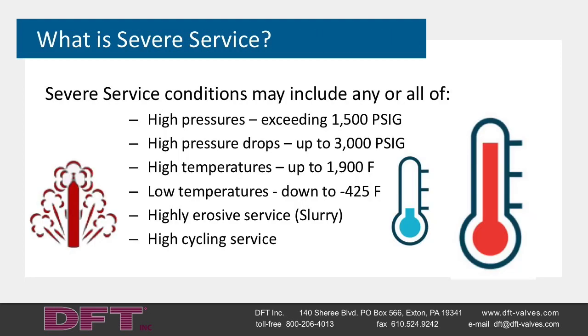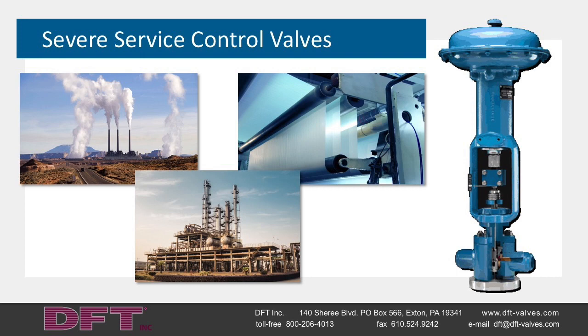What is severe service? Severe service is any service that results in excessive wear and frequent maintenance. Severe service conditions may include any or all of the following: high pressures exceeding 1,500 PSIG, high pressure drops up to 3,000 PSIG, high temperatures up to 1,900 degrees Fahrenheit, low temperatures down to negative 425 degrees Fahrenheit, highly erosive service, slurries, or high cycling service. Severe service applications tend to be very hard on equipment and require very unique and specialized products: severe service control valves.